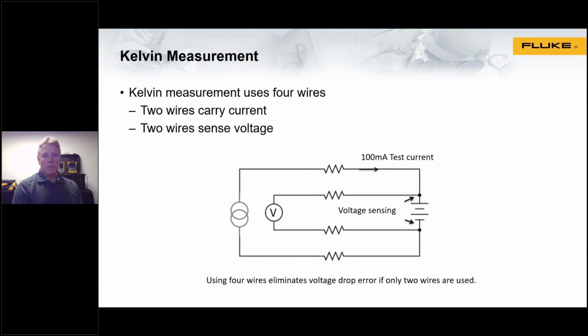Here's the way a Kelvin measurement is used. We use a test current, and we're measuring a voltage to be able to calculate resistance. If you look at these leads here and these leads here, there is a resistance associated with those leads. Think of it as test lead resistance. If you have ever used a multimeter, you know there's a couple tenths of an ohm of test lead resistance. Battery internal resistance measurements are in the milliohms, so test lead resistance would present a huge error. Actually, it's much, much larger than what you're trying to measure.